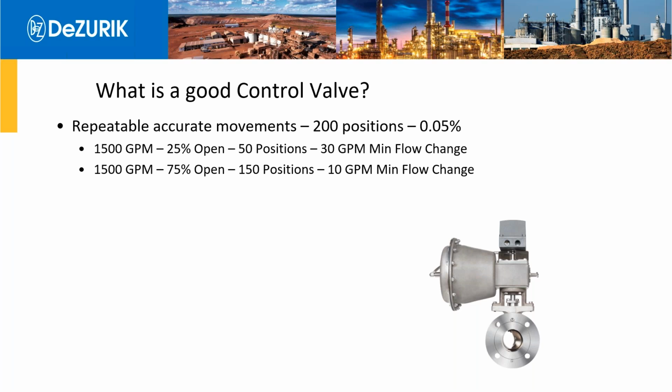Conversely, if you have that same system with 1,500 gallons per minute maximum flow, and you would size that control valve for 75% open, you'd have 150 positions. That would give you 10 gallon per minute flow change every time you move that valve. So from a loop tuning standpoint, you're going to have a much more stable loop if you can make smaller incremental positions. And from a process control standpoint, it'll be much easier to maintain your process control standards by making smaller changes with the control valve.